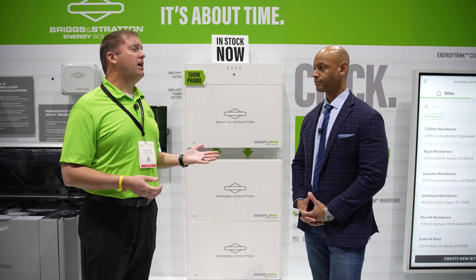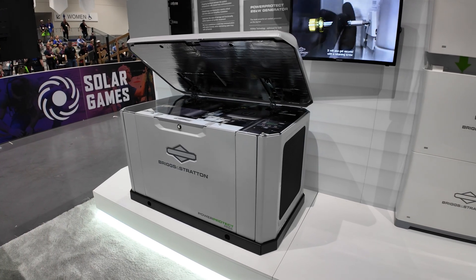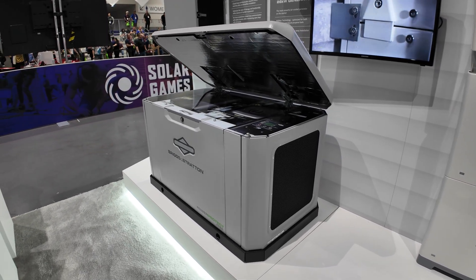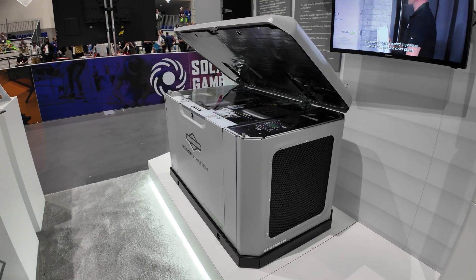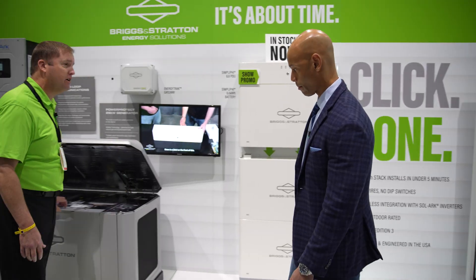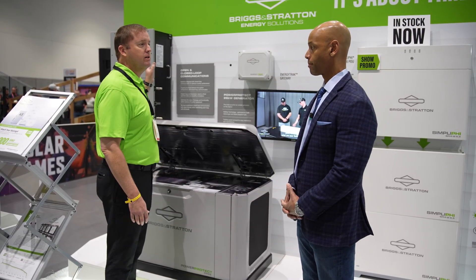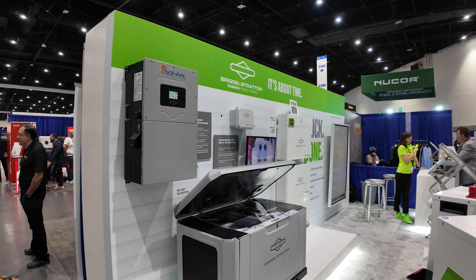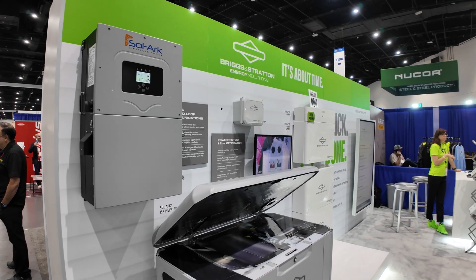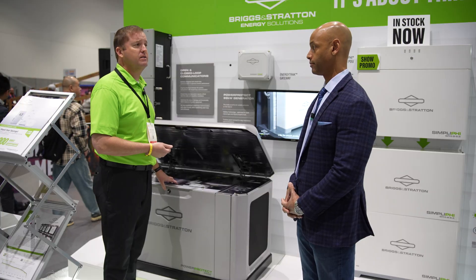Yeah, absolutely. Off-grid has always leveraged generators to charge up the batteries during the winter, during those dark months where you're not getting the solar you're looking for. Briggs & Stratton is still making millions of gas engines every year. What we're looking at is a 26K generator — either propane or natural gas. We use a hybrid inverter like Sol-Ark that can detect the state of charge; once the batteries get low, we charge up the battery then shut the generator off, saving fuel, noise, runtime, and maintenance.